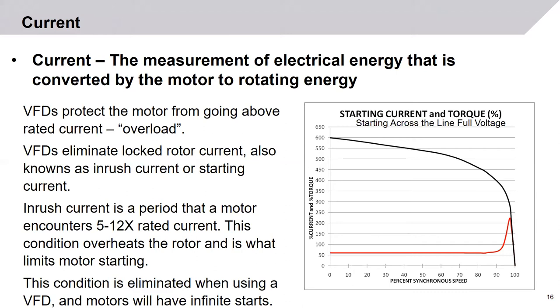Since the motor never sees such high inrush current when on a VFD, this condition is eliminated and motors will then have infinite starts. When a motor first starts, it will see six times its rated current, and as it gets up to speed, it will slowly decay until it reaches its rated operating point. For a low-inertia pump application, this could only be 8 to 12 seconds. For a high-inertia fan or mill, it could be as much as a minute during which the rotor is getting excessively hot.